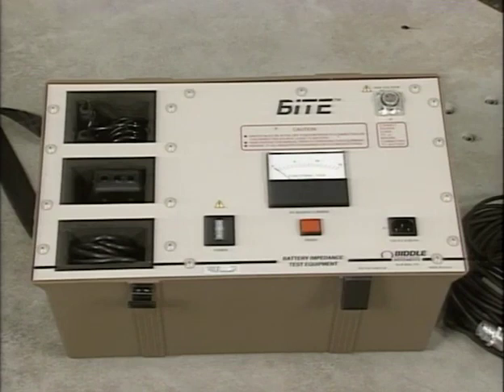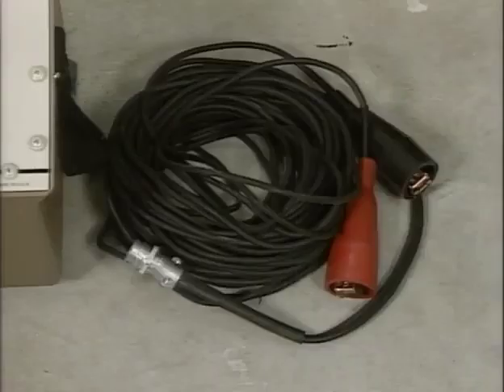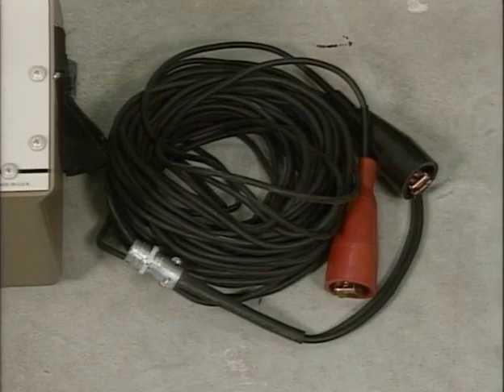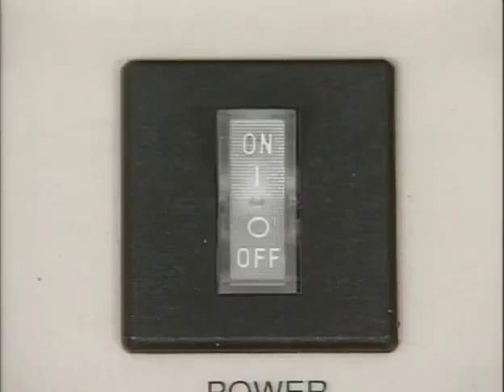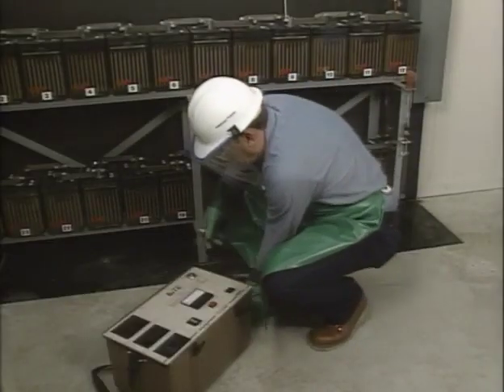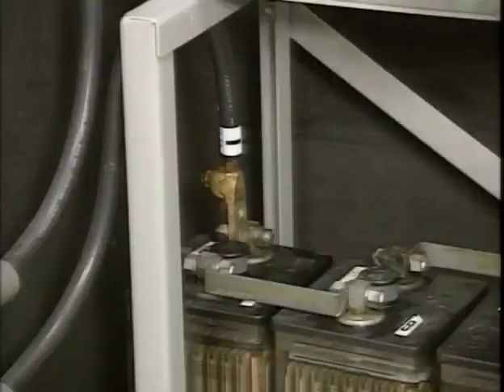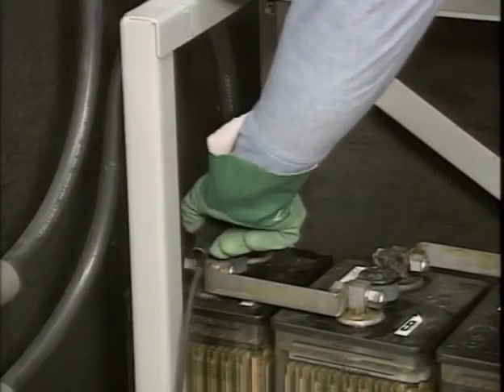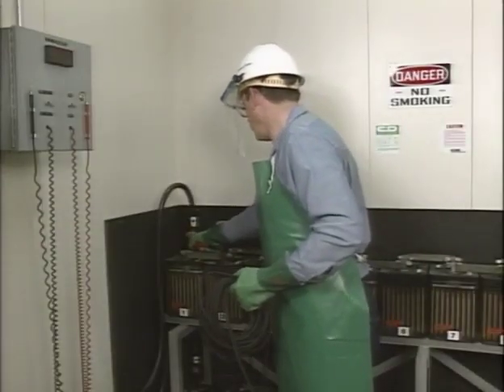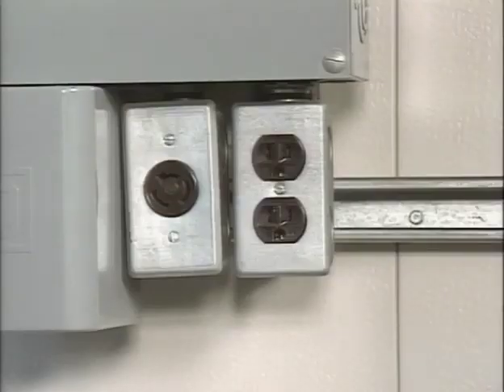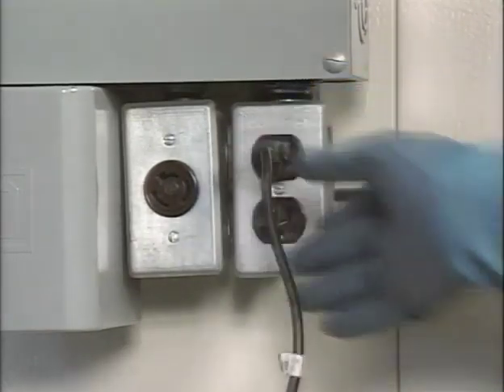One component of the test set used to measure impedance is the transmitter. The transmitter generates a low-frequency AC current. A second component is the source leads, which are used to apply the AC current from the transmitter to the battery. The transmitter should be switched off when the source lead connections are made. The leads are first connected to the transmitter, and then to the negative terminal on the last cell of the battery, and to the positive terminal on the first cell. After the source leads are connected, the transmitter is plugged into a standard AC outlet and switched on.